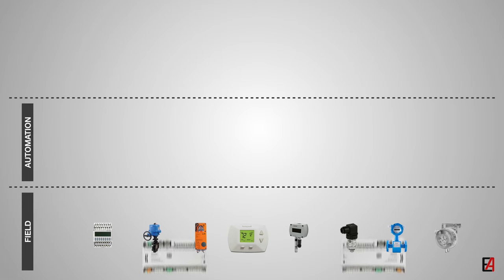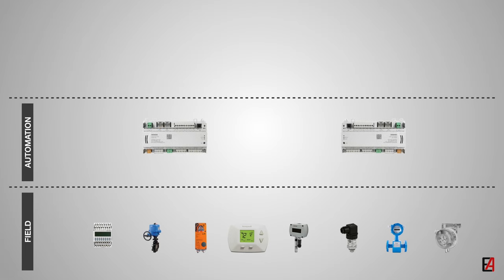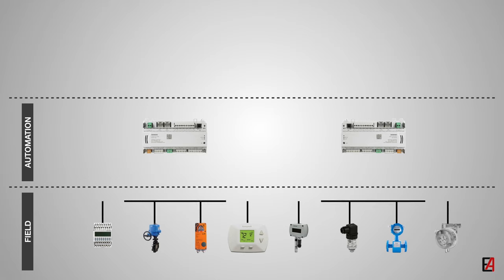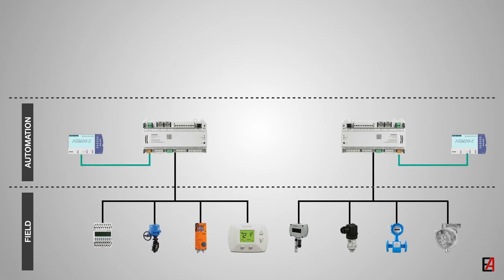Next is the automation level. This can be called the brain of the building management system. It consists of compact and modular DDC controllers. The DDCs process the inputs from the field devices and take action to provide comfort to the building occupants and safety and security to the building equipment. The DDCs are freely programmable. The controllers can be connected to a handheld operator terminal to control or monitor the field equipment at the field level without the requirement of the management system.